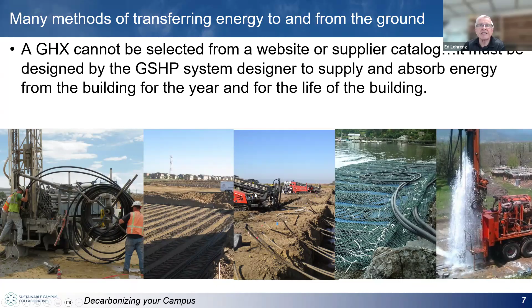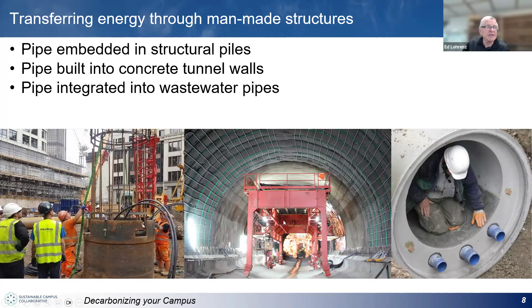What's happened in the last several years is larger buildings often have fairly deep piles. This is a project in New York City where the piles go down about 120 feet, or 35 to 40 meters. You put the pipe in there and fill these with concrete, so you're touching a lot of dirt. Or if you're near a subway, you put pipe in there, or in sewers, you can take heat and dump it into the sewer and the dirt surrounding it.